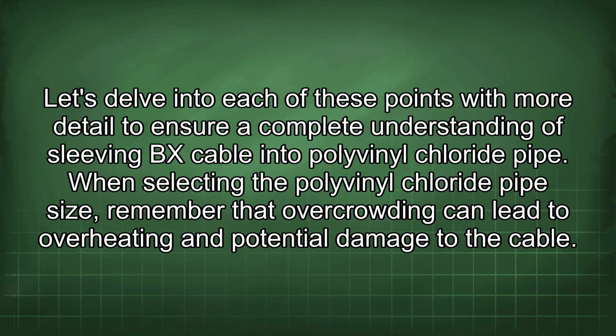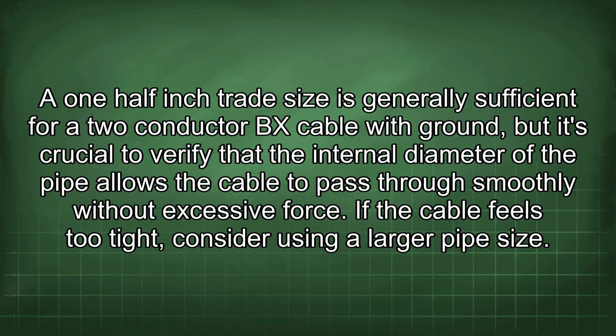When selecting the polyvinyl chloride pipe size, remember that overcrowding can lead to overheating and potential damage to the cable. A 1/2 inch trade size is generally sufficient for a two-conductor BX cable with ground, but it's crucial to verify that the internal diameter of the pipe allows the cable to pass through smoothly without excessive force. If the cable feels too tight, consider using a larger pipe size.